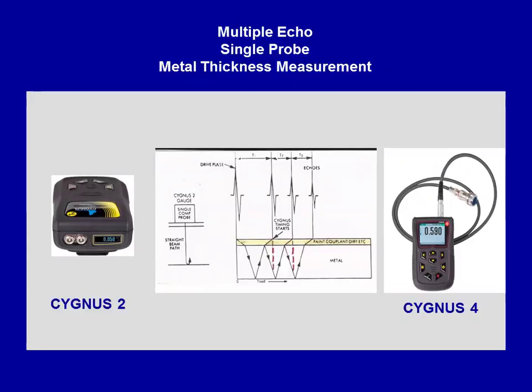But at the same time, the sound's going back down in the steel. Okay? So we're waiting for this to get through to trip the clock, but the sound's moving down. So by the time the clock turns on, it's actually here. So we go through the same cycle a second time. Same thing. And as you can see, what we end up measuring is just one cycle of sound that's trapped between the two walls of the steel. We then look at the second echo, we look at the third echo, we match the timings between the second and third echoes. When they match, and they must match exactly, then the instrument will display a measurement.